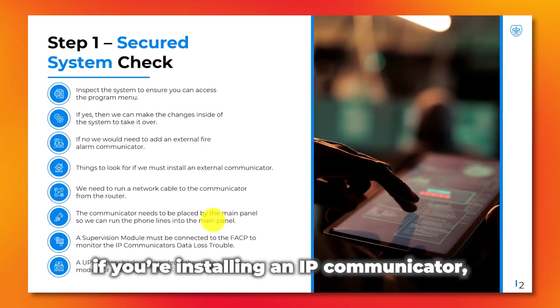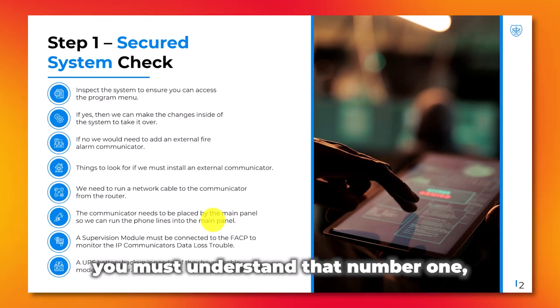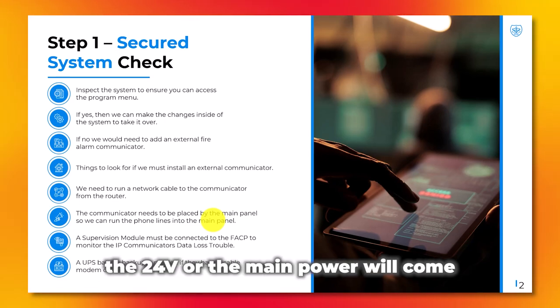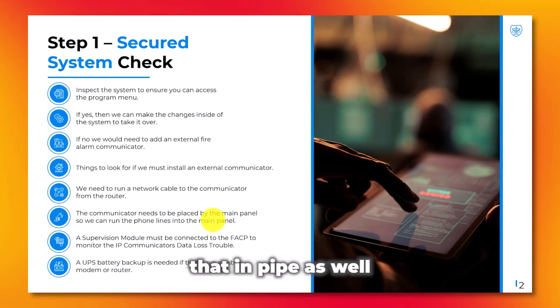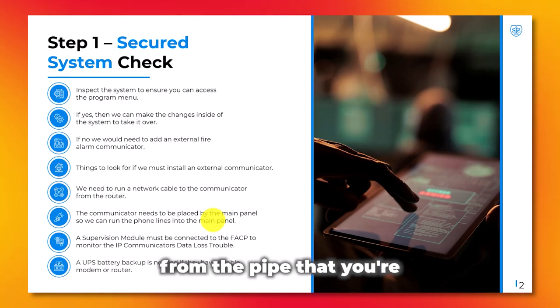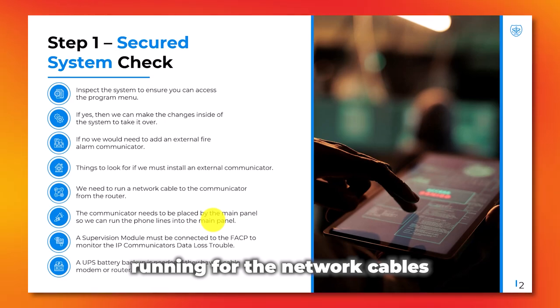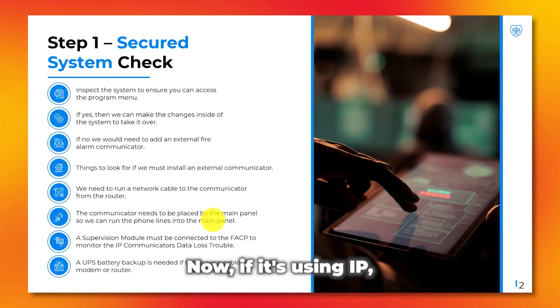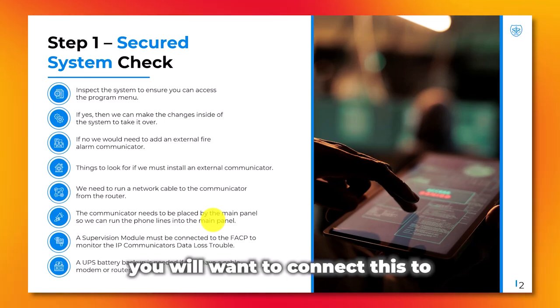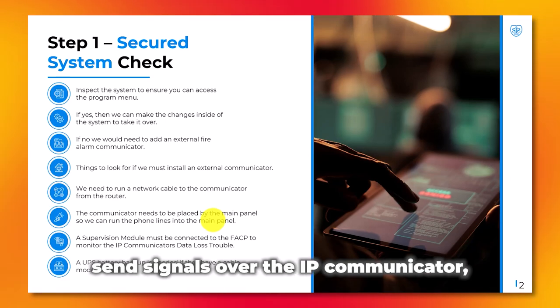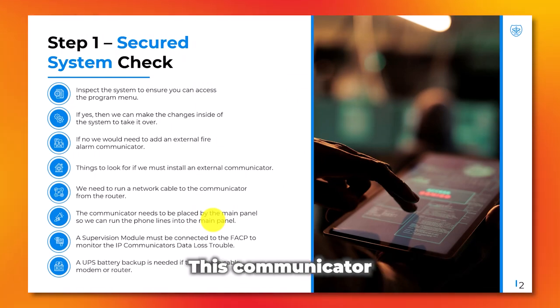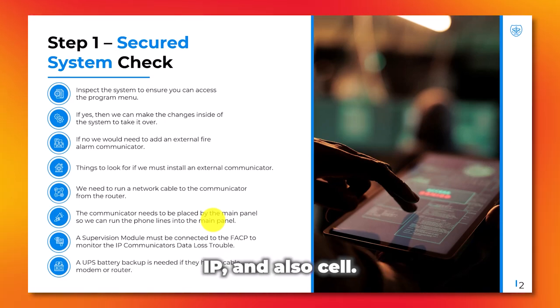Now if you install an IP communicator, understand that the 24 volts or main power will come from the fire alarm panel, and that has to be encased in pipe — in a separate pipe from the one you're running for network cables or phone line cables. If it's using IP, you will want to connect this to the customer's router or switch so it can communicate via IP, send signals over the IP communicator and also over the cell communicator. This communicator has four types of communication: phone line one, phone line two, IP, and cell.